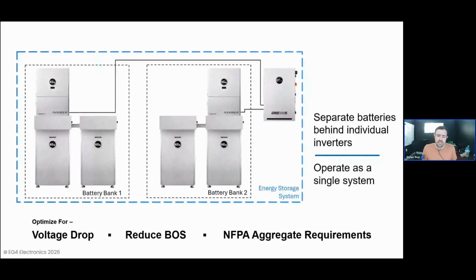And then, like I said, certainly you're going to run into this with NFPA fire zones where, for example, in a garage, they generally want to see 40 kilowatt hours or less. So if that customer wants to do 80 kilowatt hours or 100 kilowatt hours, we might be able to deploy some of those batteries in a garage, some additional batteries at an outdoor location, and again, still have that entire system operate as a single solution when it's delivering power for use in the customer's home. General caveat here is I would recommend an equal number of batteries be deployed behind each sub bank here, just so we don't see significantly more drawdown from a percentage perspective in one bank versus another. But again, a really, really great way to get a little creative and enable deployment of the system that the customer wants to see with as minimal issue as possible for the site conditions.